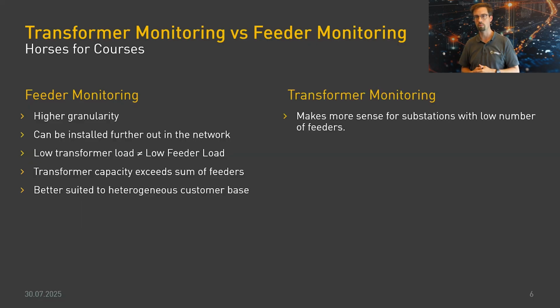So what's the flip side? Where does transformer monitoring make the most sense? It makes more sense in substations with a low number of feeders. There are plenty of situations where you maybe have just 3 feeders coming off a transformer, and in that case the differentiation between those 3 feeders may not be that relevant relative to the size of the transformer. So it might make sense to say: if I measure that transformer, that's enough to tell what's happening below that point.